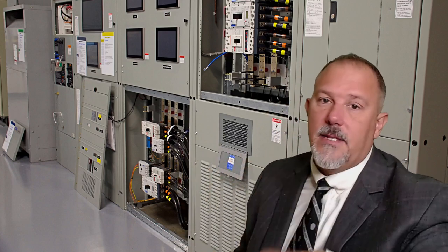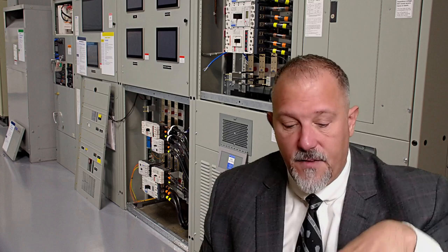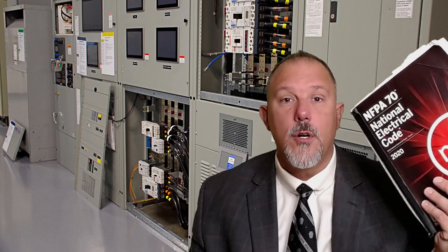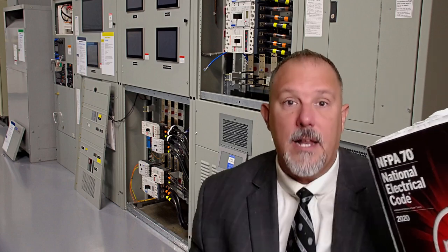It's really easy when you look at something and you see all the rust and the holes and the bent metal. It's what you don't see in some cases. You might look at a piece of equipment like this and say it looks like it's brand new. But if it was misapplied from a National Electrical Code perspective, you're exceeding the short circuit current ratings. Your conductors haven't been sized correctly.